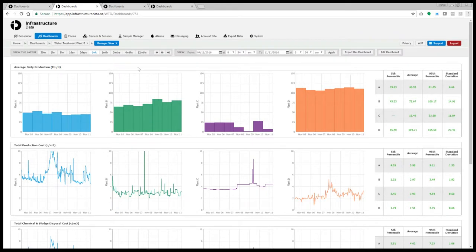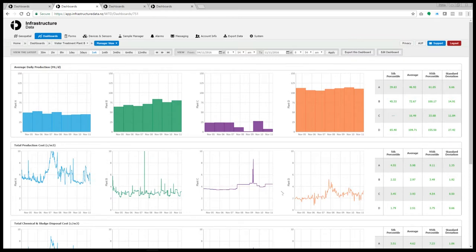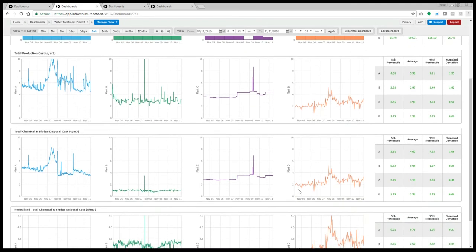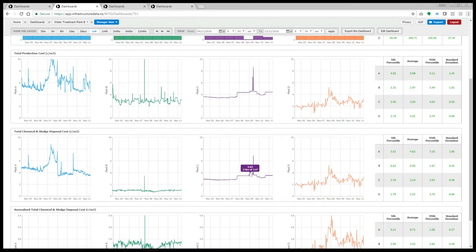Now let's take a look from a management perspective. In this example, we want to compare operational cost across four plants. First of all we look at daily production — if we know the total production cost, we can maximize production from the plants that are cheapest to run if they're serving a linked distribution system. This is not a static situation: one plant may be cheaper to run under certain conditions but not others, so this type of dashboard facilitates real-time decision making. We can gain further insights by drilling into the data, starting with total production costs covering power, chemicals, and sludge disposal. We can remove the power component and look at sludge disposal and chemical costs across the four plants. However, we're still not really comparing apples with apples because these plants may be treating different source waters.